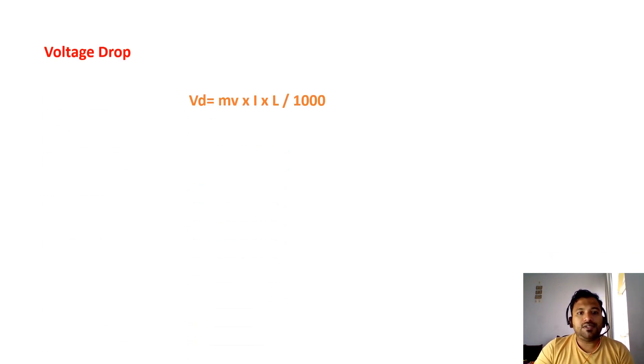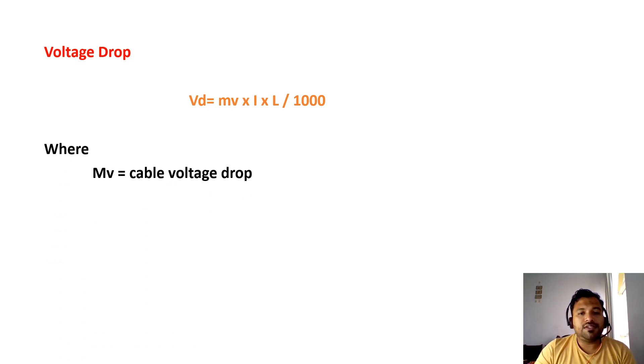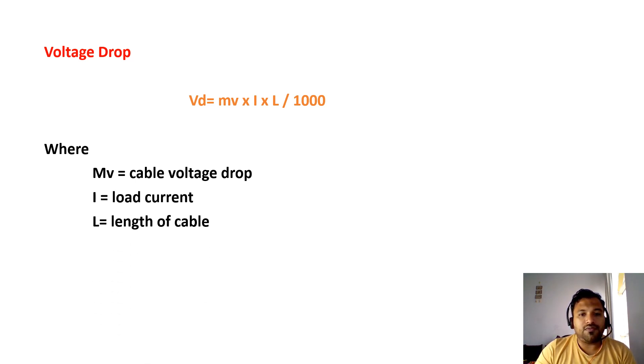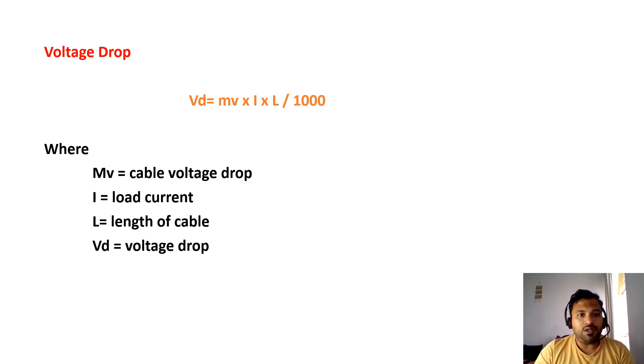Basically, the voltage drop formula is: VD = MV × I × L / 1000, where MV is the cable voltage drop, I is the load current, L is the length of cable, and VD is the voltage drop. With the help of this formula, we will calculate voltage drop calculations.